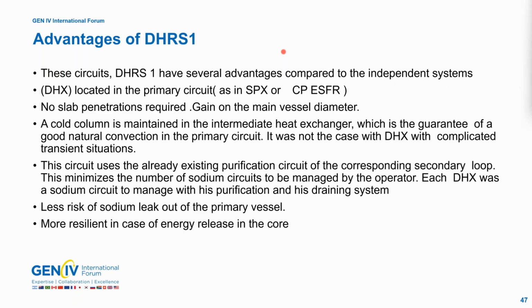There are several advantages in comparison with the independent DHX system that was located in the primary circuit in Superphénix or in CP ESFR. We have no slab penetration, so we have a gain of vessel diameter. We have a cold column that is maintained in the intermediate heat exchanger, and so natural convection with the core is operating very well, very quickly. The circuits use the already existing purification circuit of the secondary loop, so we don't add new loops of sodium. And we have less risk of sodium leak out of the primary vessel because we are not in the primary vessel. And we are more resilient in case of energy release in the core. Thanks.